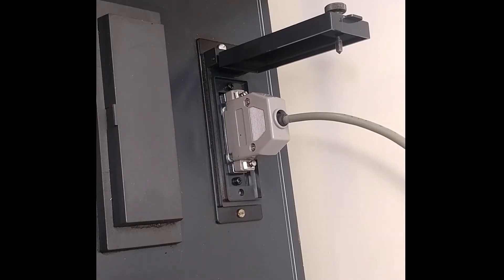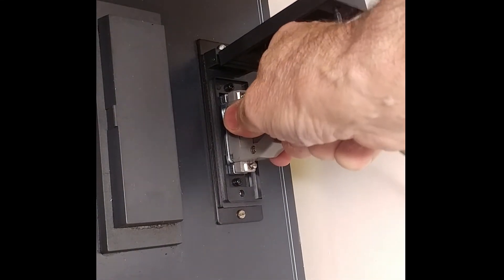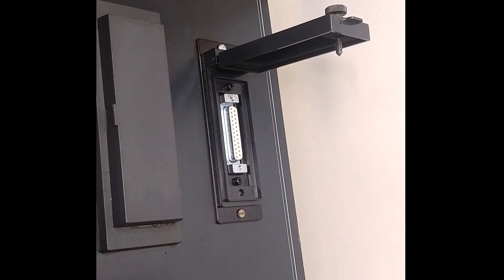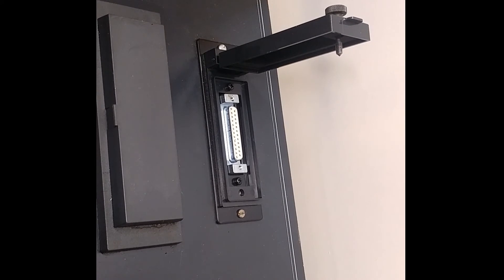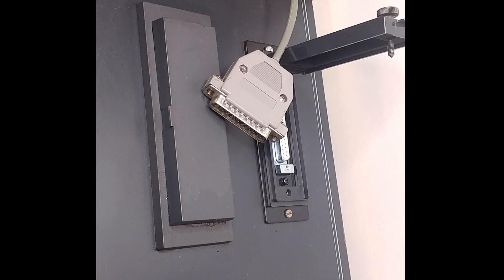In order to send or receive files between the CNC and the PC, there are a couple of things that need to be checked first. First and foremost is the cable plugged in. You'd be surprised how many people forget to check this. By the way, never leave an RS232 cable plugged into a machine when you're not using it. It provides a nice path for a high voltage spike, such as a lightning strike, to get into the machine. Always unplug it when you're not using it.